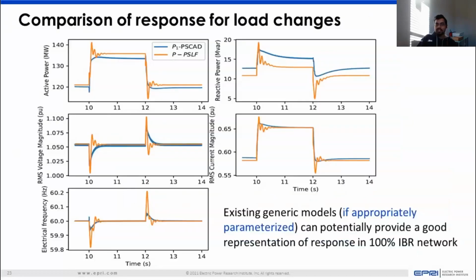This is the response we got from the two models. In the EMT domain, the blue curve shows a load increase and decrease with virtual oscillator control in the 100% inverter-based resource network. The orange curve is the same system, but in the positive sequence domain with the generic models available today in PSSE or PSLF, for the same load change. The models have to be appropriately parameterized, but we find they can potentially provide a semblance of the response seen from detailed EMT simulations.